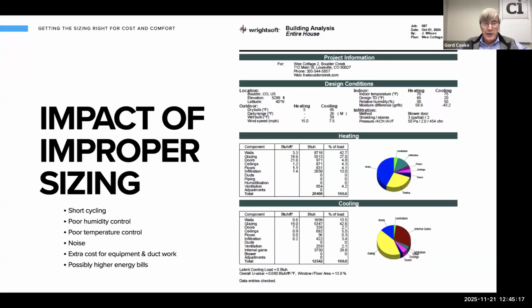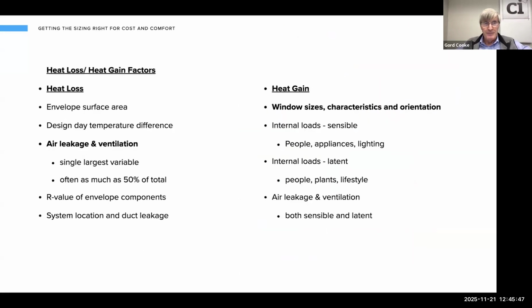On the left-hand side, what we end up with is if we don't size correctly, we get short cycling, poor humidity control, and from this conversation, extra costs from equipment and ductwork. If you want to get to all electric, you're enabled to do all electric if you can get the heat pump sizing, A, smaller, and B, correctly sized. And third, C, balanced. You'd like the heating and cooling loads to be closer together, if you will, is what we'd like to get to. And in terms of heat loss, heat gain factors, on the heat loss side, you'll see it includes the envelope, the surface area, how cold is it outside. I've highlighted air leakage and ventilation because they are the biggest portion. The instantaneous load on the coldest day of winter is the single biggest component, is always the air leakage. And so we keep that in mind.